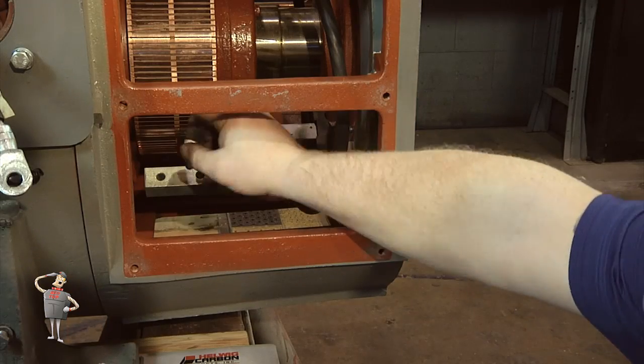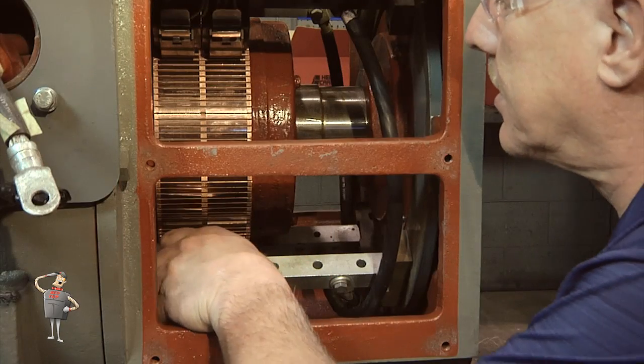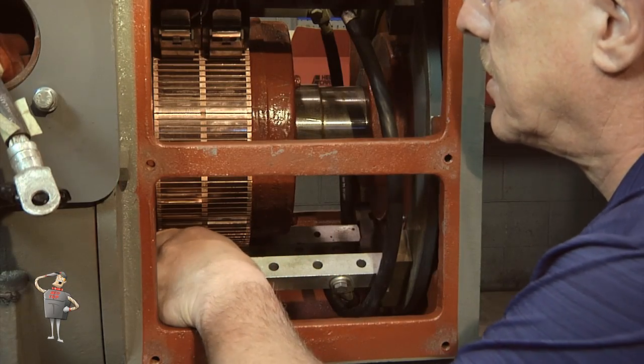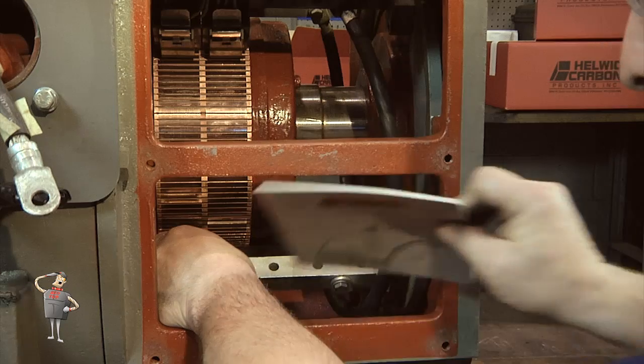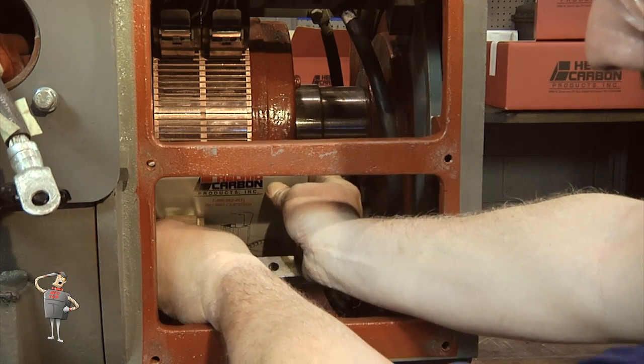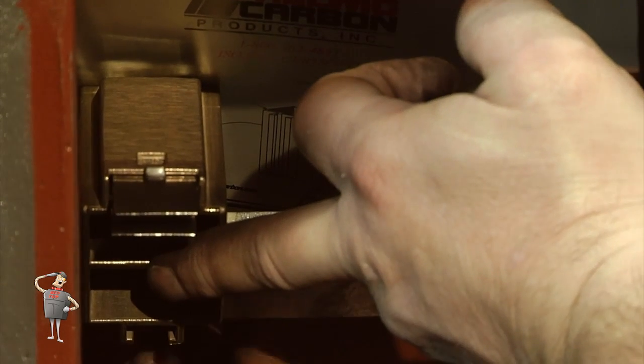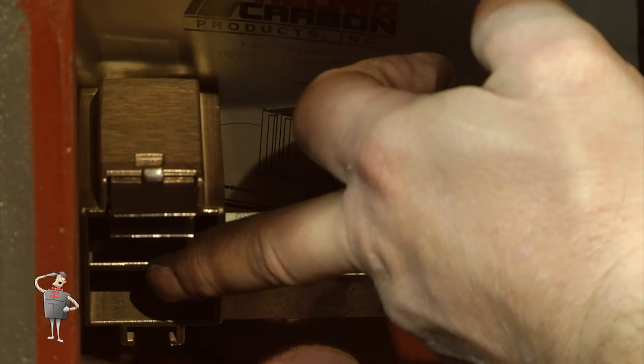Be sure the terminal connections and holder mounting plate are cleaned. Place the protective Helwig commutator pad on the commutator, then put the brush holder on top of the pad. Adjust the height, which should be 125 thousandths of an inch, or the thickness of the commutator pad, and secure the holder.